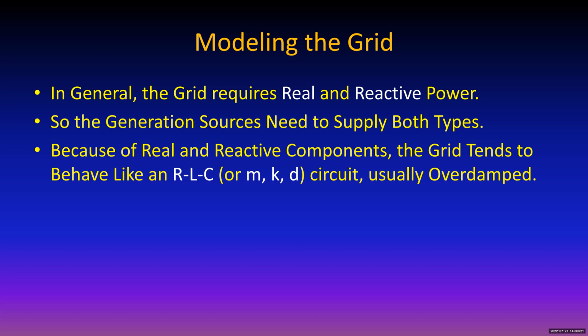Mechanical engineers know about mass spring dashpot systems, electricals know about RLC circuits. The idea is that you can lead to instability if you have fast changes where you have all of these components in a system. Now, R is mostly what the load is, and the more resistance you have in the system, the more damping you have, and it's less likely the system's going to go unstable. So the modeling of the grid likes to model the amount of resistive load as a measure of the stability of the grid.